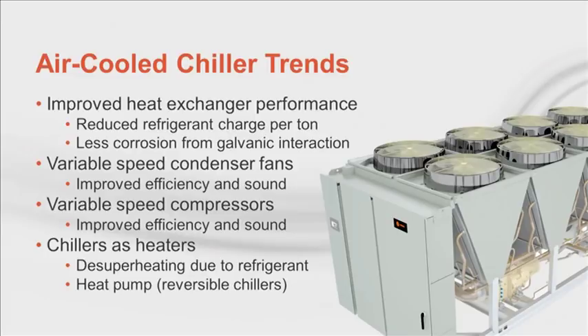Finally, the change to refrigerant 410A created more desuperheat, the amount of heat you can withdraw from the refrigerant gas at a given pressure before it begins to condense. Not all air-cooled chillers use 410A. Another option is to use dual condensers or reversible refrigeration circuits to make the chillers become air source heat pumps. This is a lot more common in Europe.